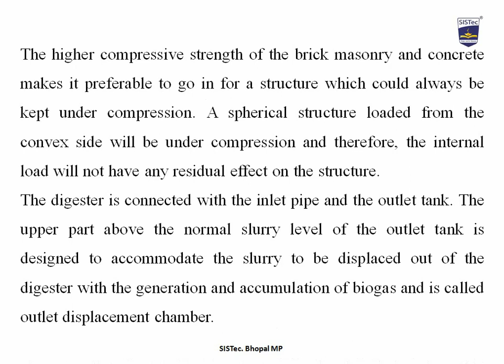The digester is connected with the inlet pipe and the outlet tank. The upper part above the normal slurry level of the outlet tank is designed to accommodate the slurry displaced out of the digester with the generation and accumulation of biogas, and is called the outlet displacement chamber. The size of these plants is recommended up to 6 cubic meters per day. The different components of the Deenbandhu model biogas plant are as shown in the figure.